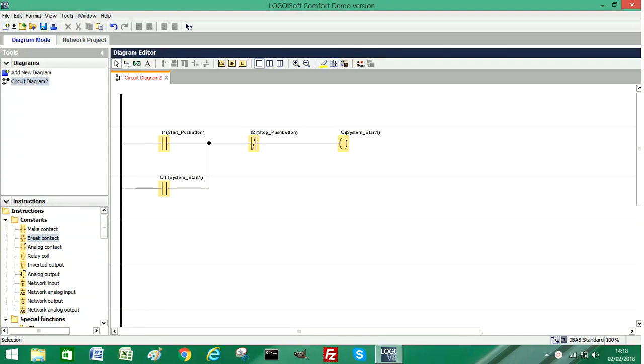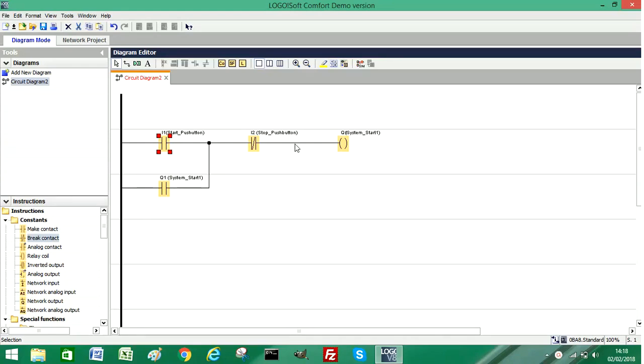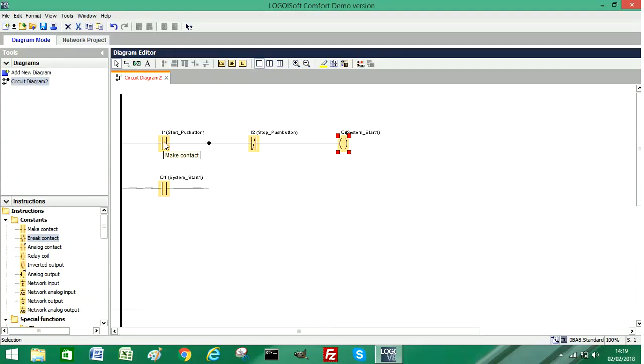So first of all you can see the logic that I've created here. We have a start push button, a stop push button, and a system start - this is the output. The way this is going to work is an operator of the machine or system would press the start push button, the system will start and latch itself on, because this input is the same tag as the output. And when the operator decides they want to stop the system, they will push this stop push button.